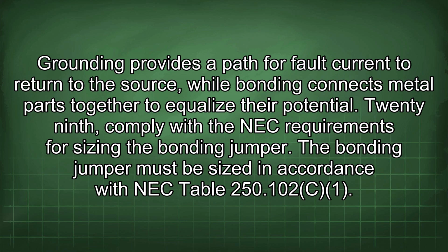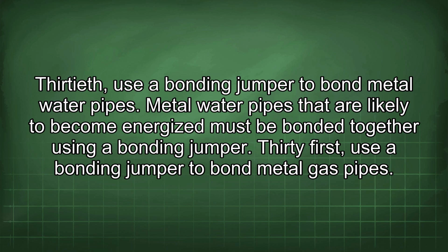29th. Comply with the NEC requirements for sizing the bonding jumper. The bonding jumper must be sized in accordance with NEC Table 250.102(C)(1).